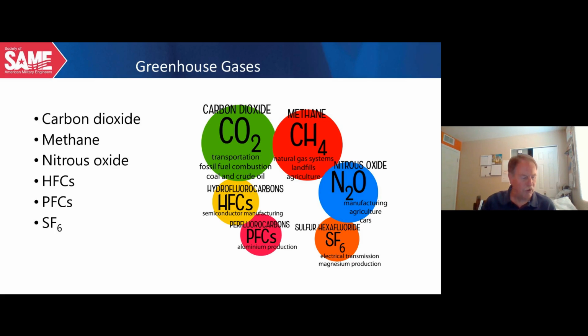So when you talk about utility grade circuit breakers, 345,000 volts, 500,000 volts, 750,000 volts, this gas is used to suppress the arc that obviously is generated when you open up a feeder that's got maybe 1,000 amps flowing through it at 500,000 volts. So certainly very important, and also in magnesium production.